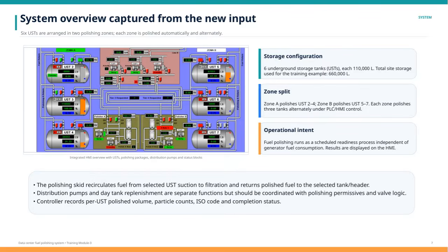Here's an overview of the system based on the new input. We have 6 underground storage tanks, or USTs, each with a capacity of 110,000 liters, giving a total site storage of 660,000 liters for training purposes. These tanks are divided into 2 polishing zones, Zone A and Zone B. Zone A handles USTs 2 through 4, while Zone B manages USTs 5 through 7. Each zone polishes 3 tanks, alternating automatically under PLC and HMI control.